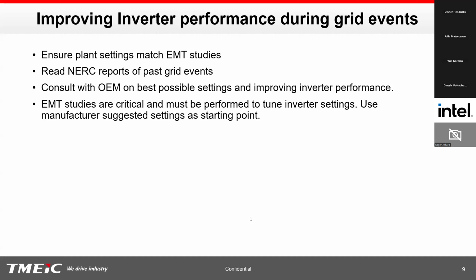In a lot of cases, we see that EMT studies are performed, and once it is checked off the list, the model is not really used. When we get to the field, we do not actually get feedback on what settings need to be programmed on the inverters. So we often hear that we can program whatever we want to some extent, because the study was done, there's a check off on the list of things that need to be done, and the model is often lost.